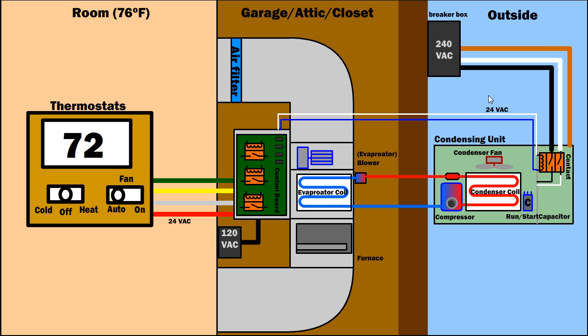So moving forward, the first thing you always have to check is to make sure that you have power. I can tell you so many times how a friend or even like my own home, like the AC doesn't work and we start looking elsewhere, but it comes back to the circuit box, the circuit panel, the junction box where there's no power going to either the furnace at the controller board or going to the condensing unit outside. So it's a very easy check. Make sure that you have power.